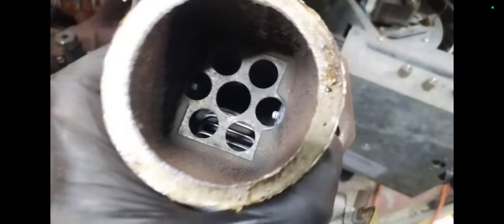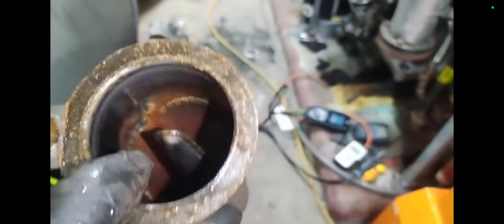Print that off. Here we have another unit with the fan out. Here's a look inside the fan. So do remember on these to check all your modules at the same time. I'm just inspecting another one. And do remember to change your gasket. I found one of these, believe it or not, loose, completely loose and not connected. And the boiler wasn't isolated and so on. And that was very frustrating because you don't need that when you're working on a boiler. And it's because it's hidden at the bottom. You wouldn't expect someone to leave it disconnected.